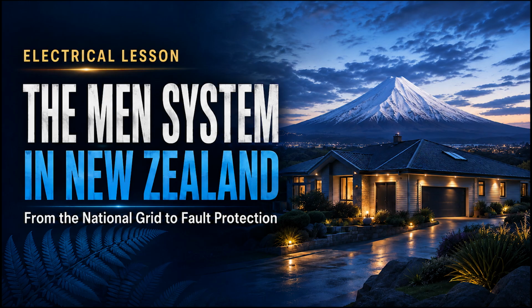If someone installs another neutral to earth link at an ordinary distribution board, some normal neutral current can divide and flow through protective earthing conductors, cable armour, metal pipes, or other bonded metal. That creates touch voltage, heating, corrosion, and RCD problems.